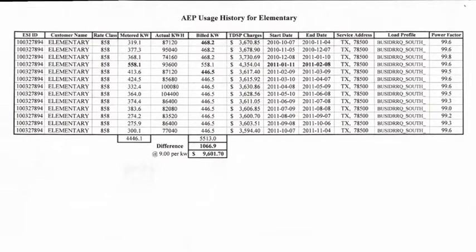But what's important here, and I bolded it where it says metered KW, it's the fourth column over. And in February, which was the bad month for this last year, you notice they've been having a demand of 319, 377, and all of a sudden there's the demand of 558 kW. Because in February we had that freeze, and all your electric strip heat came on because everybody wants to be warm. All right, so all of a sudden now, if you go over to the billed KW, which is a couple of columns over, all of a sudden their billed KW goes up to 558, but what I want to be important there is that 80% of that for the next, well, we haven't gotten to the next year, but the minimum bill now is 446 kW for the next 11 months. And if you look at the metered kW, they have some months with 274 kW demand, but they're paying double. And I put a real simple little thing down there at the bottom.